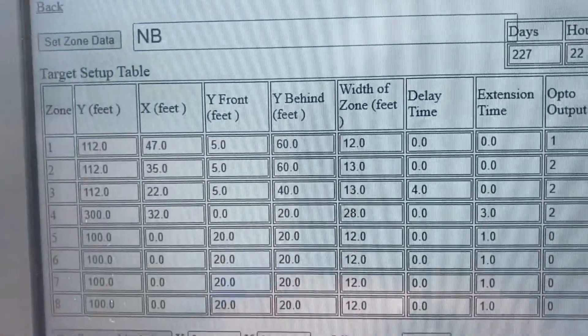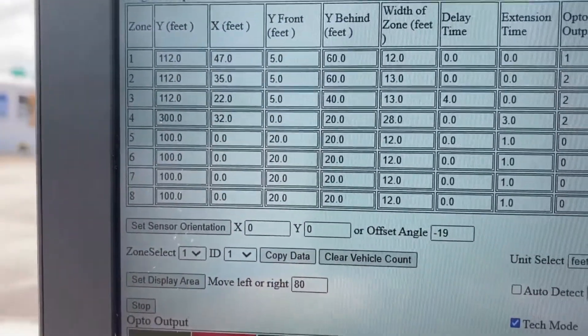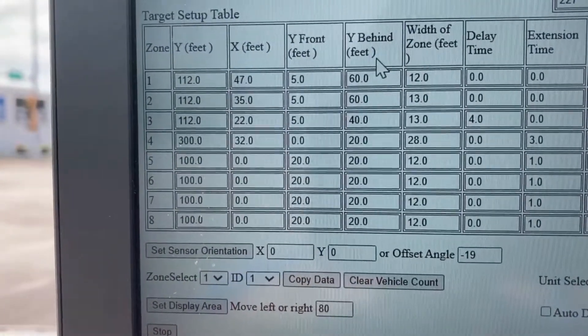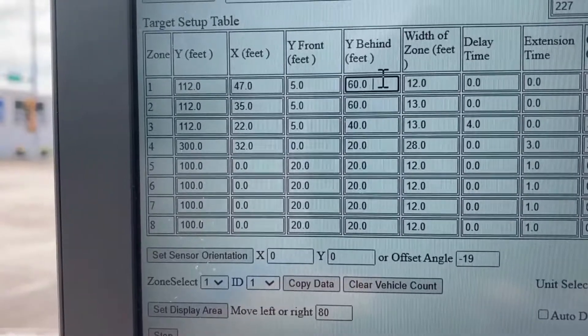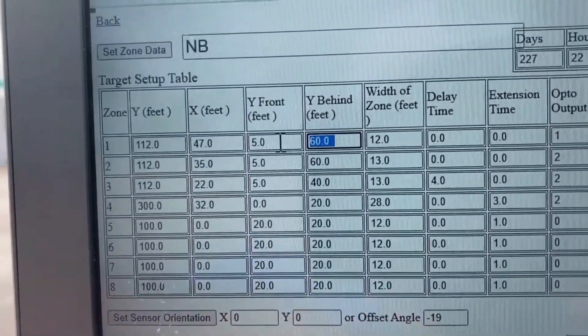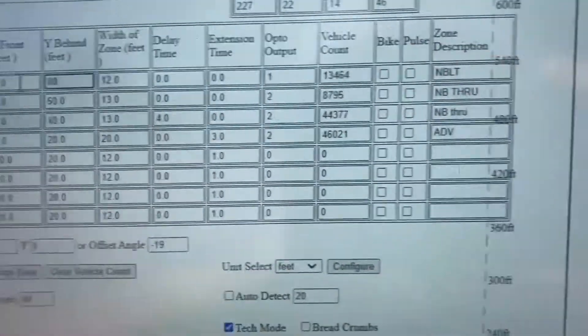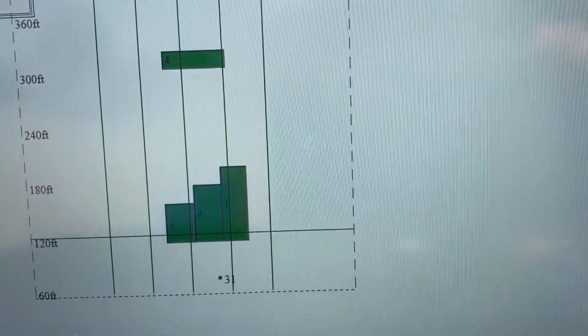I want to increase the back end of zone one — let's increase it by about 20 feet. So what we do is come up here, go to Y Behind, change that to 80, and when I hit enter you'll see that back end of that zone lengthen. There you go — hopefully the complaints from the left turn will diminish.